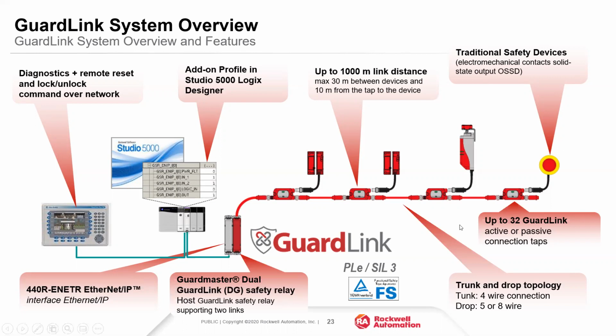Traditionally with an e-stop, you're wiring safety circuits back to a safety relay, and then you also run an auxiliary contact off of those devices back to the PLC, so you can tell which of those series connected devices are activated or faulted. With GuardLink now, all that information is pulled back through the GuardLink protocol, and you can pick it up through the add-on profile in the Ethernet module, and not have to wire that auxiliary back into the PLC just to pick up that status.